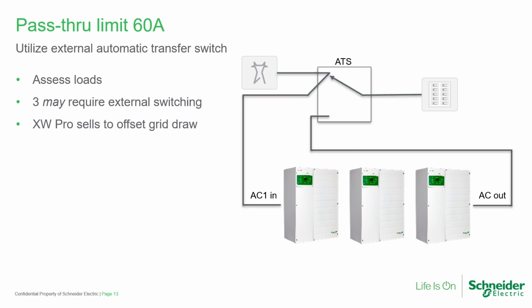Designing a system that can invert more power than pass through is not a good practice. Utilizing a whole house transfer switch will allow the sell power to offset grid demand and then switch the load to the output side of the inverter in a grid outage. Load shave and grid support do not work when using an external transfer switch.